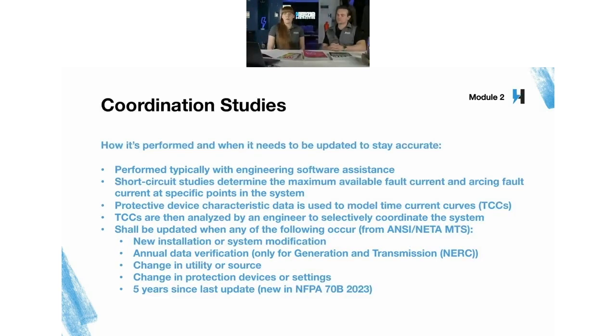So how do we perform this? Well, it's, again, typically performed with an engineering software of some kind. There's a little bit of a theme there. You'll need to model the single line diagram. Yep. You'll need to run short circuit studies. Yep. And determine the maximum available fault current, as well as the arcing fault current, which is different than the maximum, or 3-phase bolted fault current.